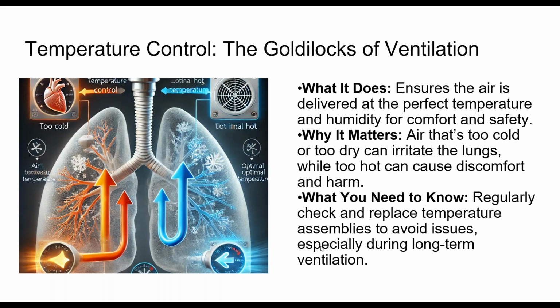Now, I mentioned rainout, and before I forget, rainout is a problem of too much humidity hitting a cold surface after the air has been warmed. Some ventilators are actually designed in a way to prevent rainout. Some accommodate it by having a heated block or a warming block somewhere in the expiratory side of the ventilator pathway, so that the air that's moist and warm coming out of the patient continues to stay moist and warm until it gets out of the ventilator or past the flow sensor. The flow sensor and the pressure sensor to some degree do a lot better if they're not gunked up over time with medication and rainout or excessive humidity.